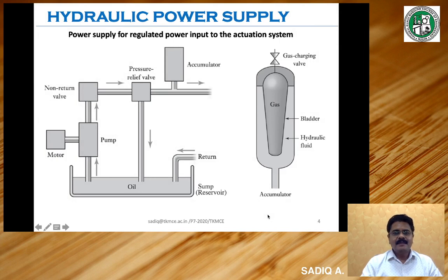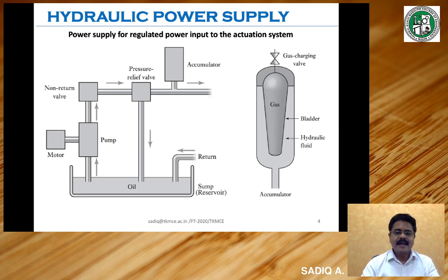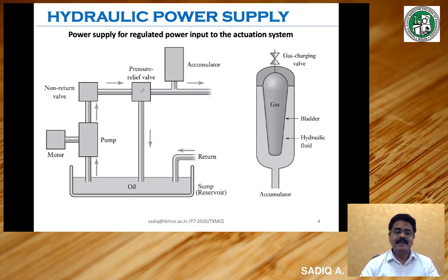Now let us see another concept in hydraulic and pneumatic systems — that is called the power supply. Power supply is meant for giving regulated power to any device. Hydraulic power supply is also meant for providing regulated hydraulic power to the actuation system. Let us see the elements in the diagram. There is a reservoir or oil sump containing hydraulic fluid, a pump driven by a motor, a non-return valve that prevents the fluid from flowing backward, and a pressure relief valve that protects the entire circuit by taking care of the circuit pressure. There is also an accumulator.